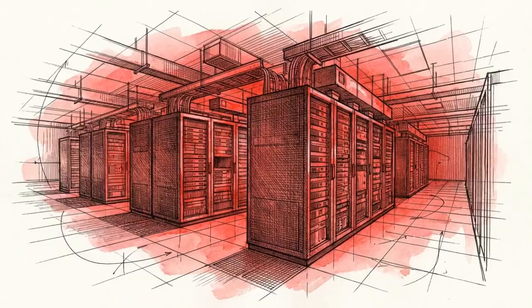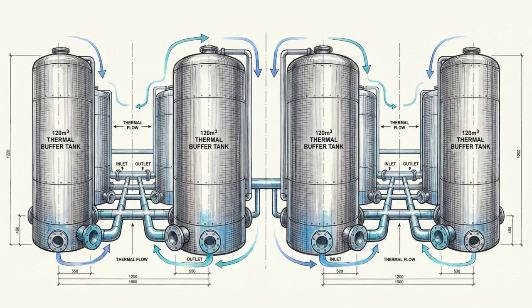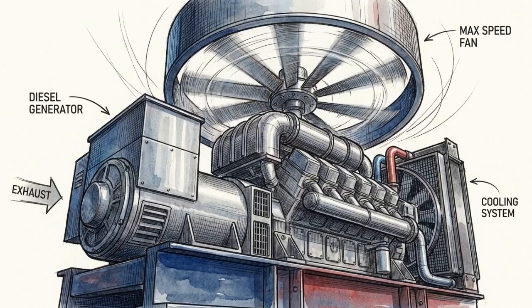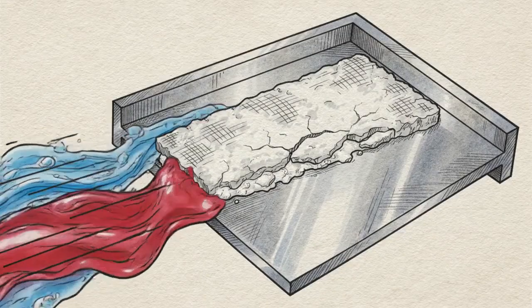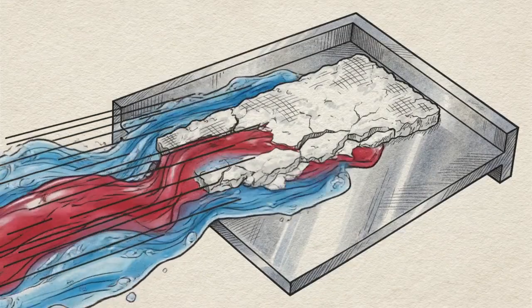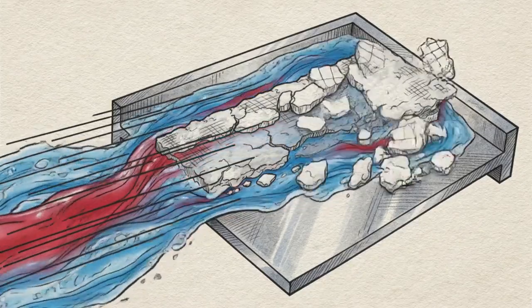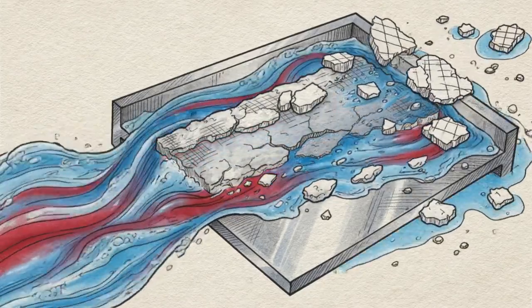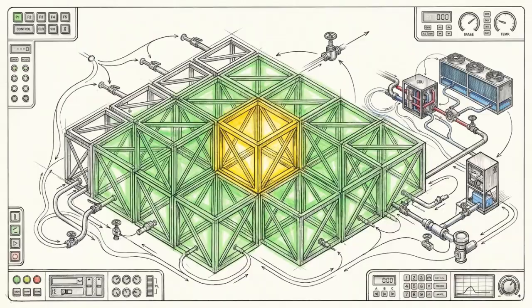During a complete utility power loss, the mechanical design takes over. Thermal buffer tanks holding 120 cubic meters of fluid provide exactly 90 seconds of full load ride-through capacity, bridging the critical gap while backup generators synchronize. To handle long-term maintenance, the plant utilizes automated in-situ clean-in-place technology. It executes low-pH organic acid flushes that dissolve calcium scale while the unit is still live, meaning a membrane cell can be rejuvenated without dropping site cooling capacity.